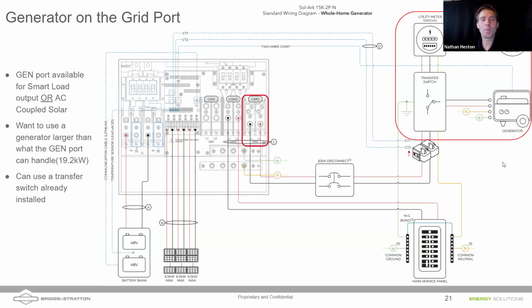Yeah, it depends. We've got a couple of questions on that. I was about to ask you what you can use that gen port for, but let me just answer that question first. So we have DC coupled solar coming in on the MPPTs. If we have DC coupled solar coming in there, the inverter is smart enough to realize, through sensing of the signal coming from the generator on the grid port, that it's not in fact grid, and it will not backfeed that generator. If you have AC coupled solar, we do want to be careful, and so you could bring AC coupled solar in through the gen port.